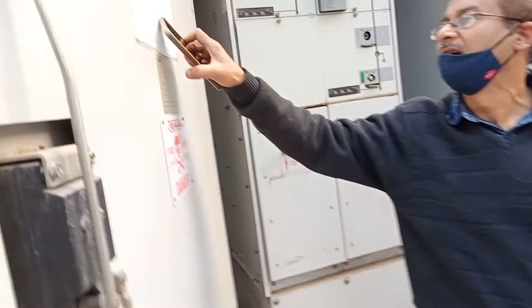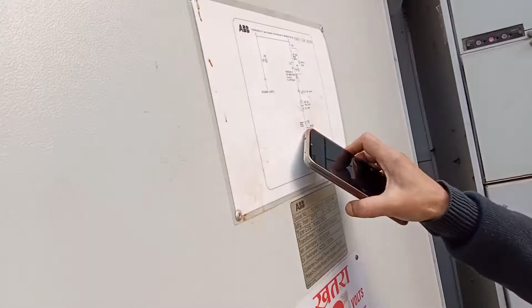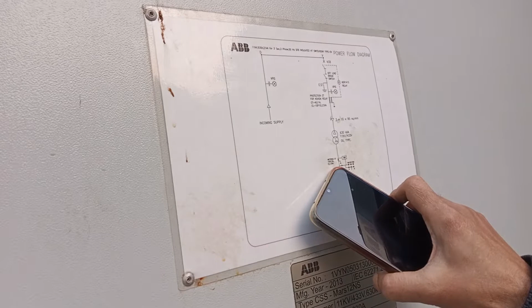Similarly, entire feeders, it's a feeder, right? 11 kV feeders are coming. Let's see the feeders again. So that is protected by arc fault and overcurrent. And the relay is designed in such a beautiful way. And that is a metering circuit here. 11 kV and down the line. See what all the current settings are. 1000 by 5 amps, and that class is 1 and 5 VA.